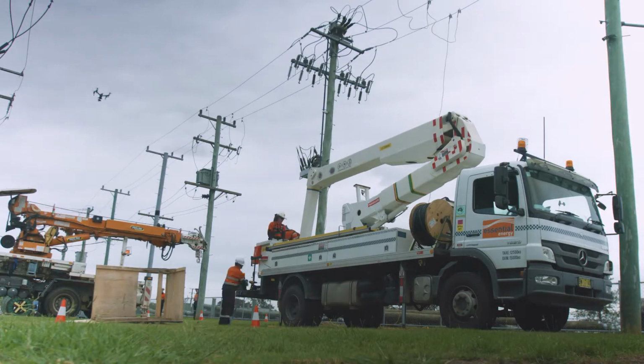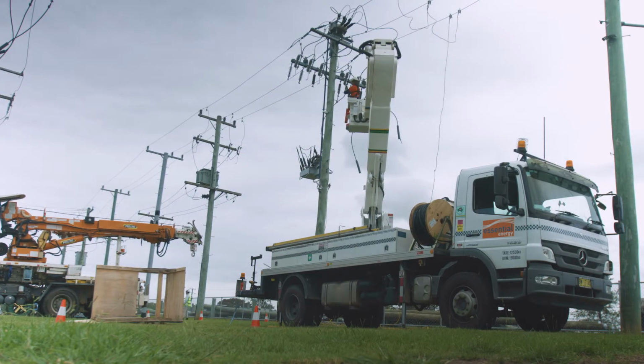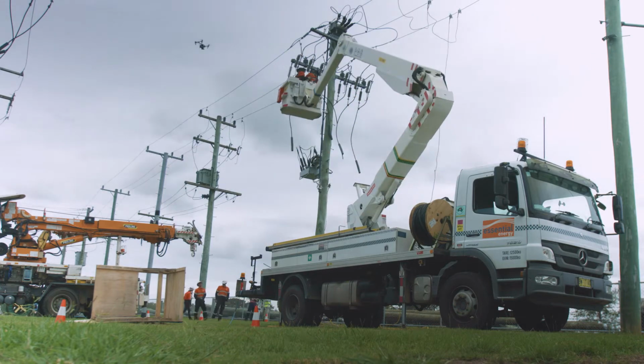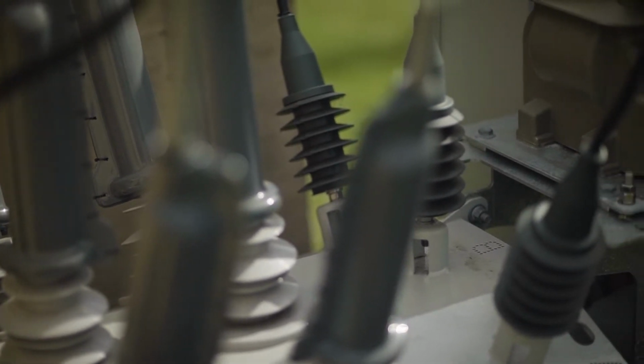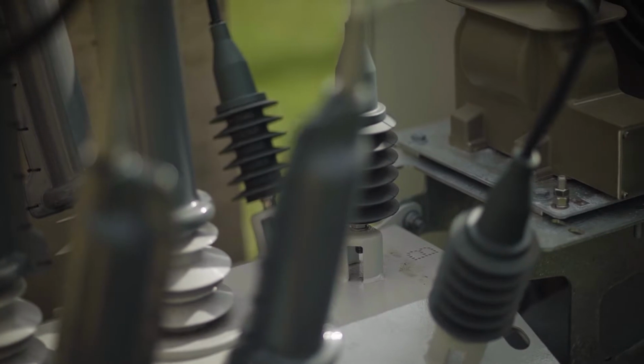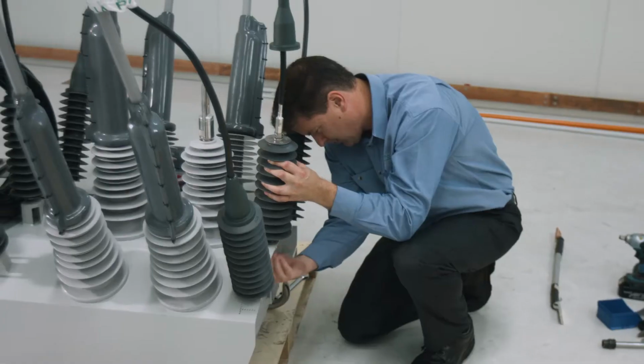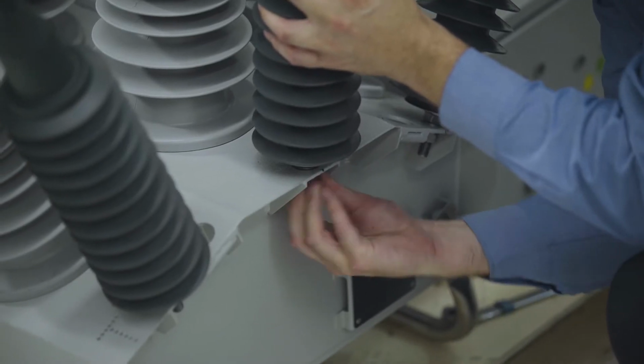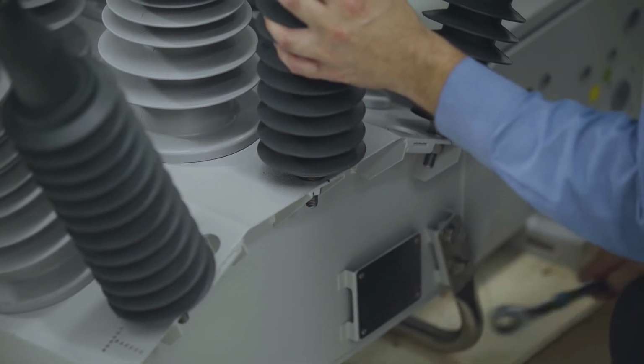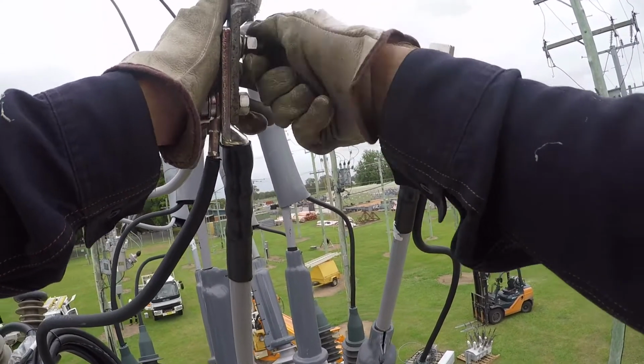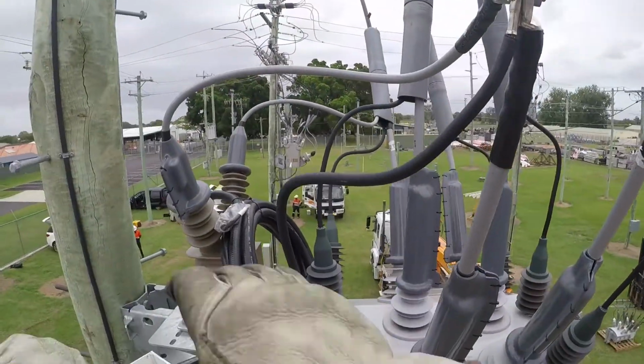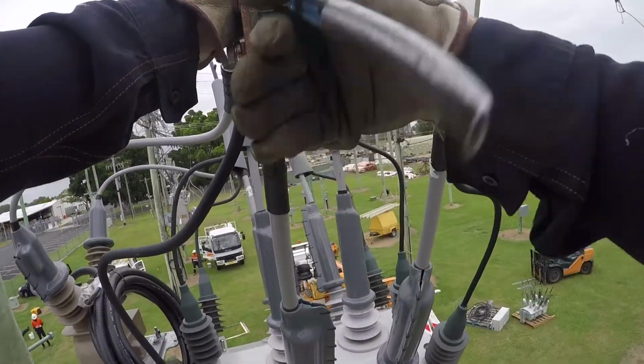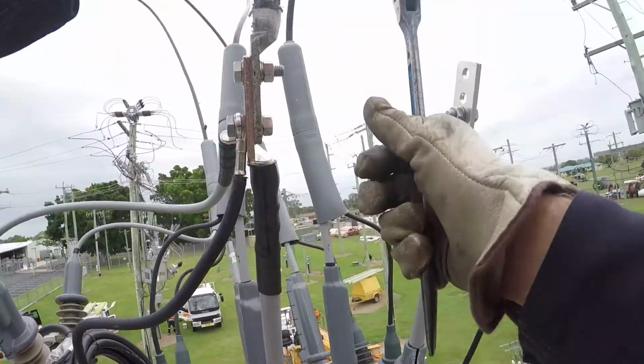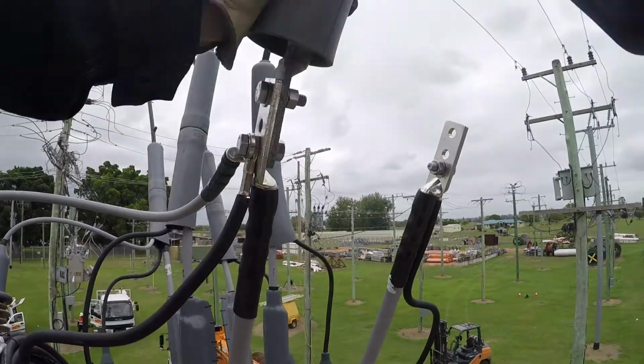Lightning strikes in power lines are common. They can generate large impulses which travel along the conductors. Surge arresters should be fitted to both sides of the recloser to protect against impulses from either direction, whether the recloser is open or it's closed. Surge arresters can be bolted directly to the tank, so the surge current is diverted to the ground through the tank. Surge arresters can be terminated onto the palm or onto the tail of the recloser using a parallel groove clamp. Any termination you use should be torqued up to 30 Newton meters.